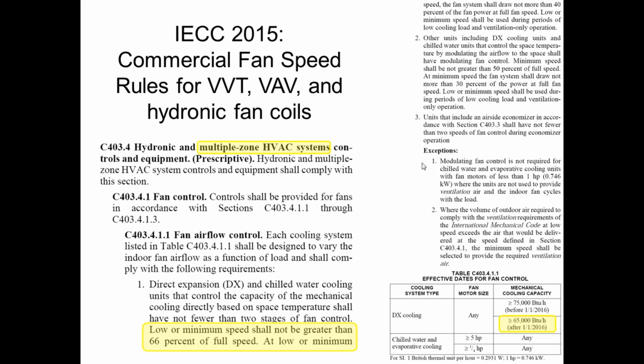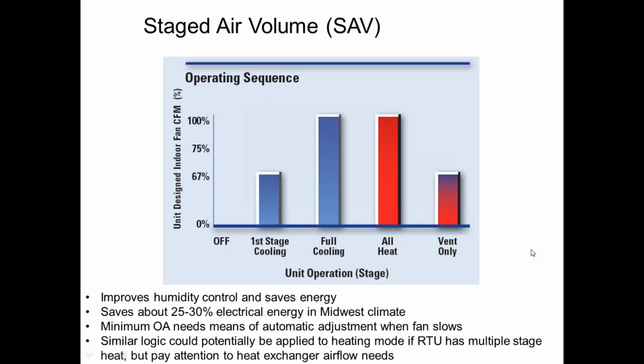The way that essentially works, the multi-stage fan, you get two speeds of fan. There is one speed that is utilized for first stage of cooling and the ventilation only mode, which is a lot of the run hours, as you know. And there's a higher speed of fan that is used for second stage of cooling, any stage of heat. Those are the two airflow set points. So essentially, if I'm in only one stage of cooling or if I'm in vent mode, we cut back from 100% of the design airflow down to essentially 2/3 of the airflow.